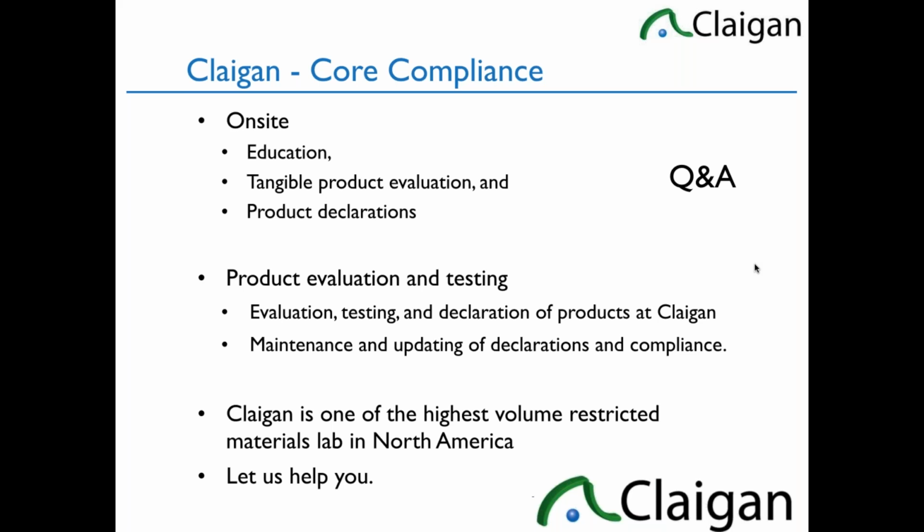The registration part is a little bit confusing because we can see, even in the standards bureau there, that for products that already have registration for safety, it's going to be another checkbox. You have to provide a test report or a technical file when you register. But that's for ones that are already registered for safety. For things that don't normally register for safety, we don't know. Medical devices will quite possibly become part of the submission to the Ministry of Health. The registration aspect is different for UAE RoHS. Everything else is technically the same.